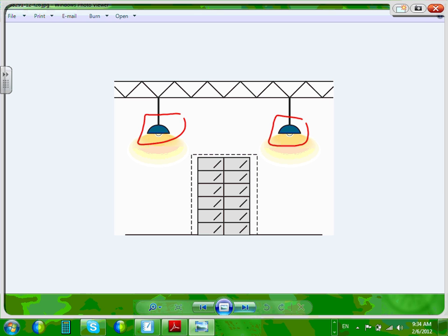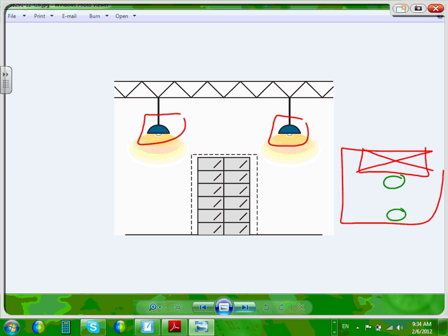So if this is your mechanical equipment, this is switchgear right here, and my option is to put only one lighting fixture right here, I would probably put my light fixture closer, right above the switchgear, not to enter the working space or dedicated space. Why? Because it wants to give you light so you can work on the equipment. So you have to have a light in the switchgear room to illuminate the working space.